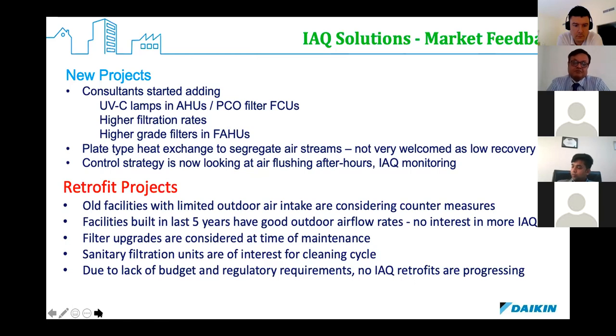But now UV lamps are being accepted—let's have space for it if we install now or in future. That's being done on a lot of projects. Filtration rate has been increased so we can have a bit more air changes, and MERV 14 and similar standards have been raised to a higher filtration level. Plate type heat exchangers were looked at, but many times when you have space constraints and the recovery rate isn't great enough, you don't get enough credit for green building. So this is one of the key factors, looking at the recovery rate.